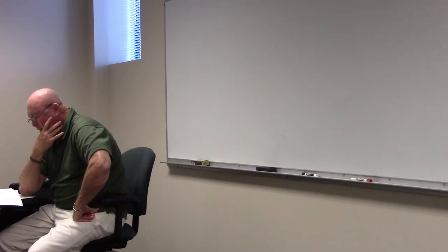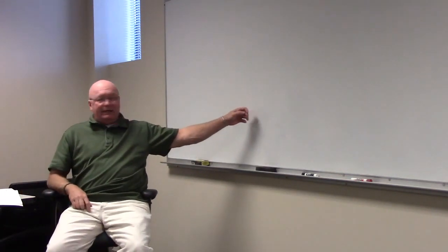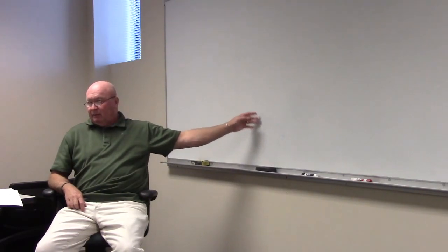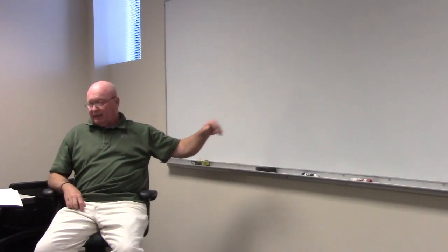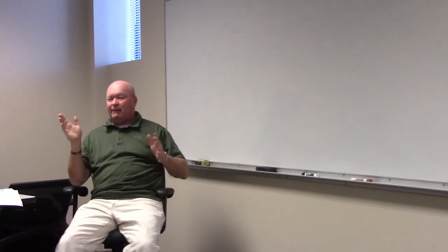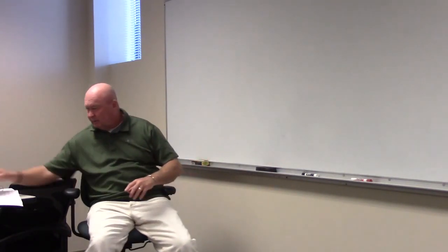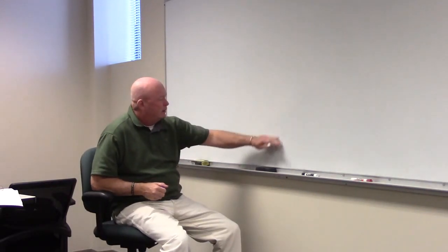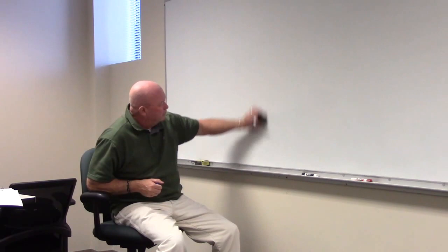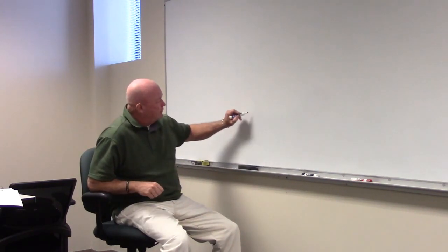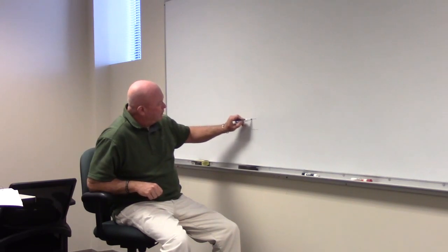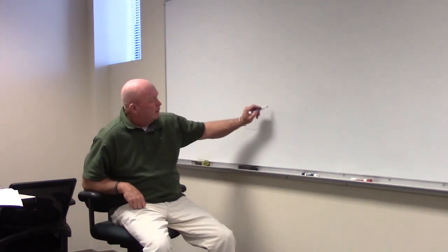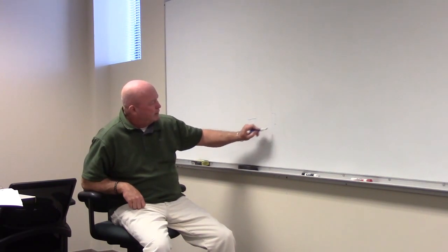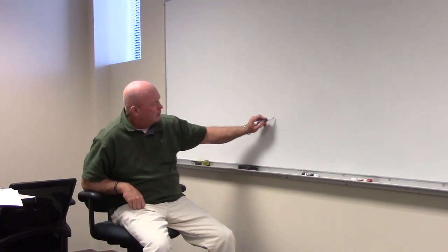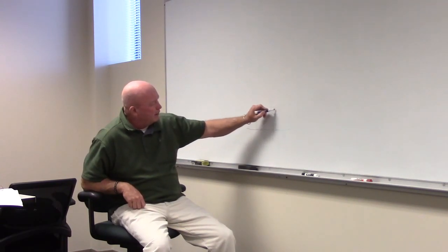And it says that it's intended to constitute a main control and means to cut off supply. So that's the purpose of that disconnect outside or circuit breaker or whatever it happens to be. But again, you don't have to have that. This is what happens with us a lot on commercial facilities. We see this more often than not. 2,000 amp service. So we have a transformer outside, don't we? We got a building, we got a switchboard inside, 2,000 amps.